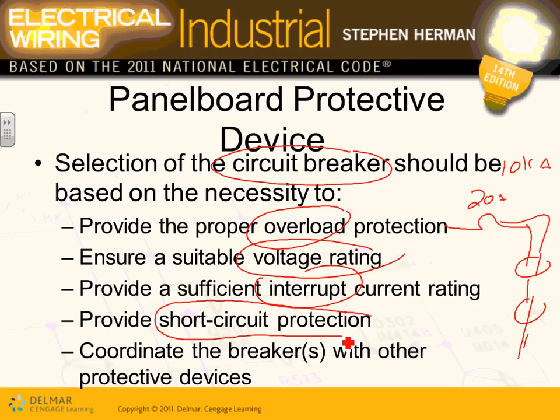Sufficient load or short circuit. And then you have to coordinate with other circuit breakers in the system. So if I have a 100 amp, 225 amp, I'm hoping that my circuit breaker here can trip before the main. That's your coordinated overcurrent protection device. Any comments, any questions?